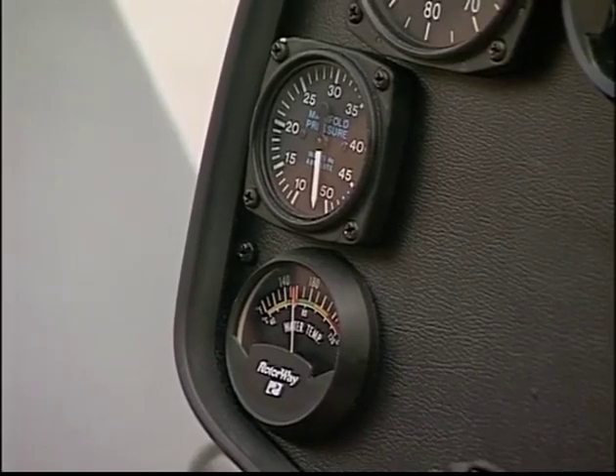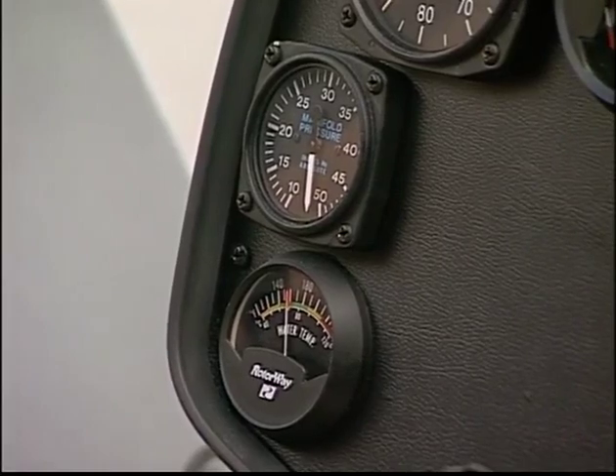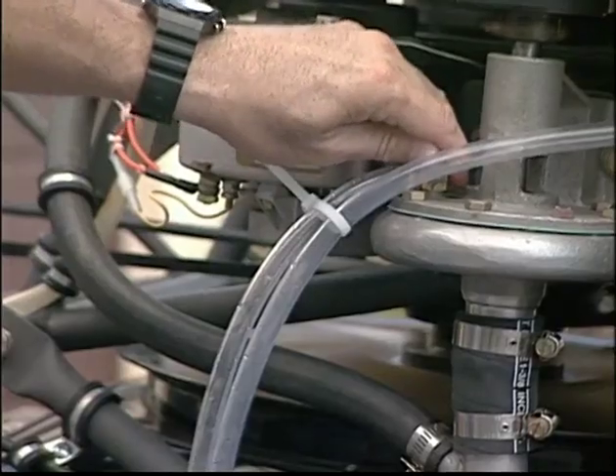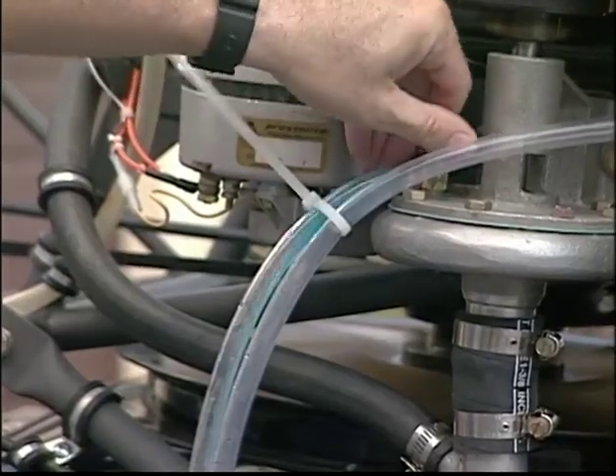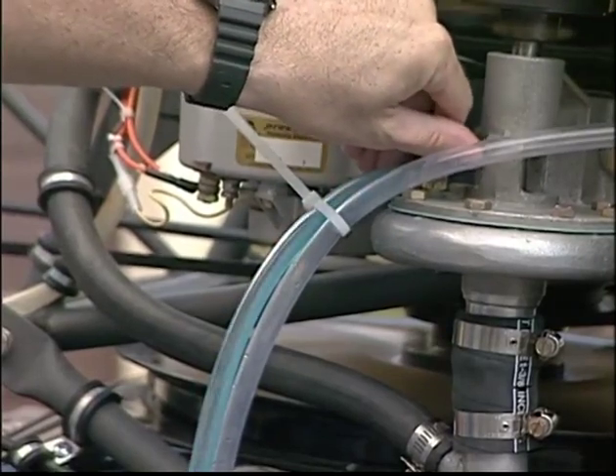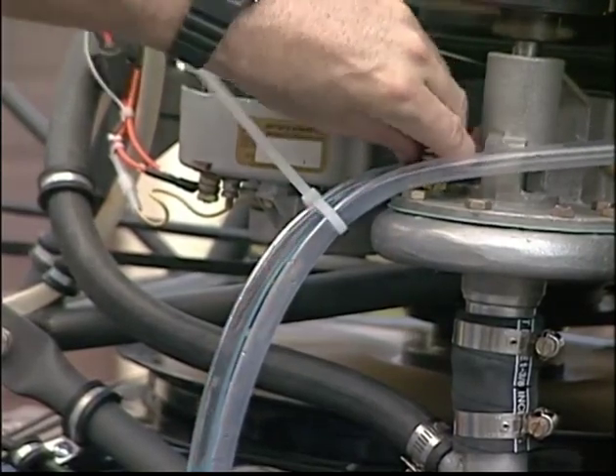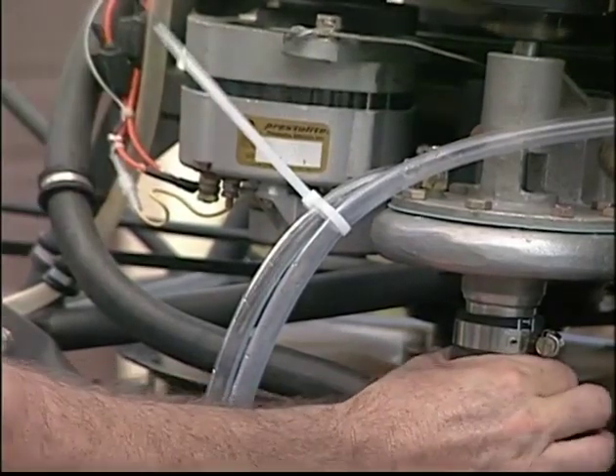Caution: water temperature must be monitored constantly during the entire initial startup procedure. It is an inherent characteristic of the cooling system to repeatedly lose the prime at the water pump during this period, causing the water temperature to increase very rapidly.